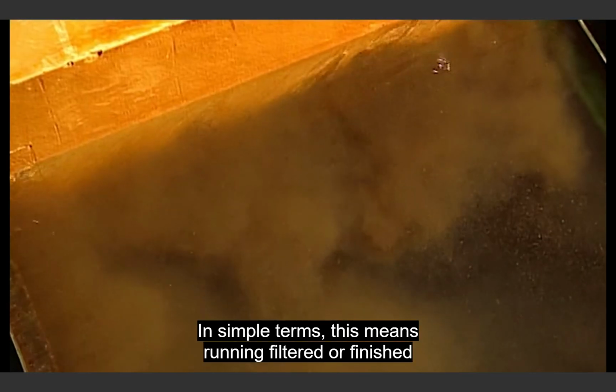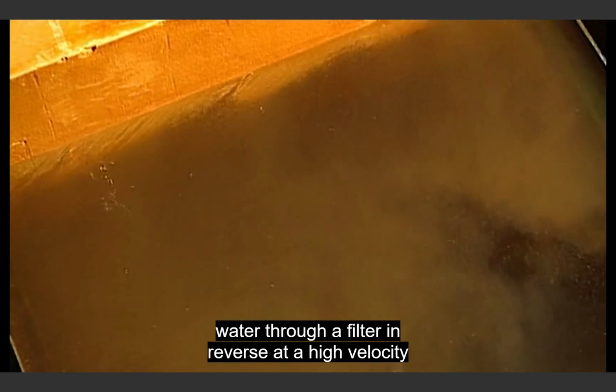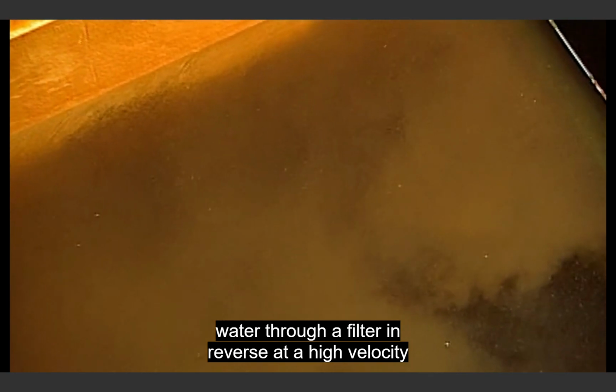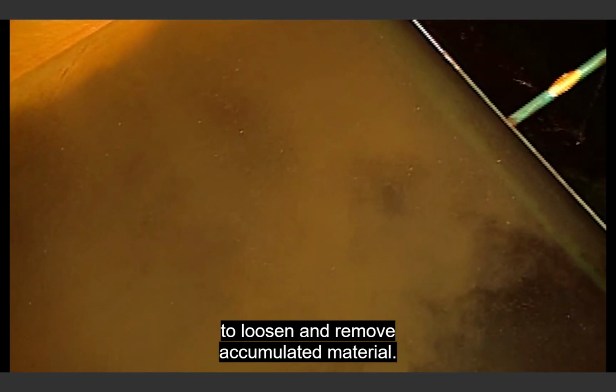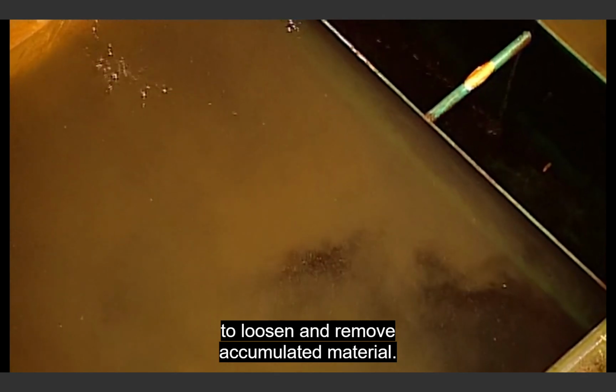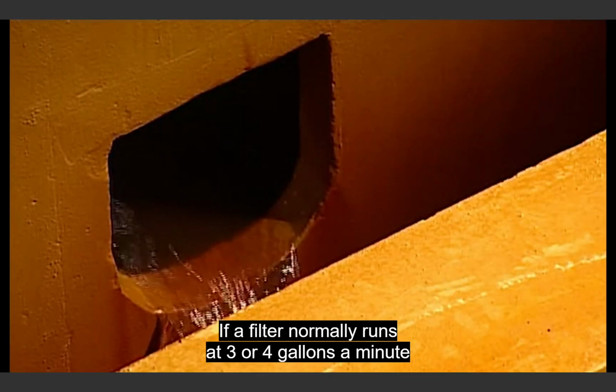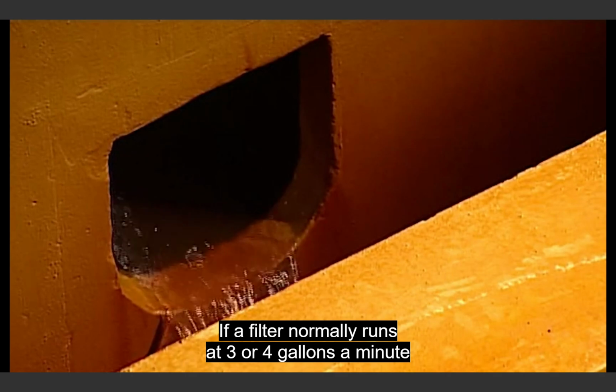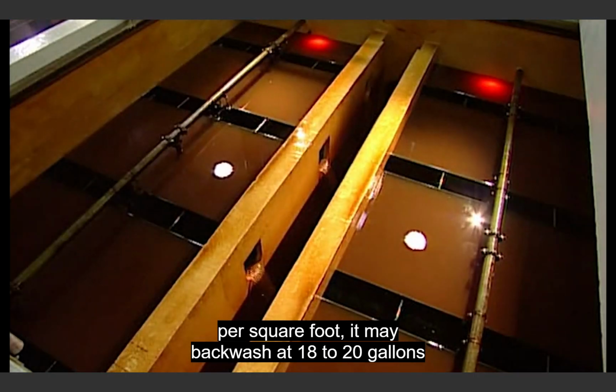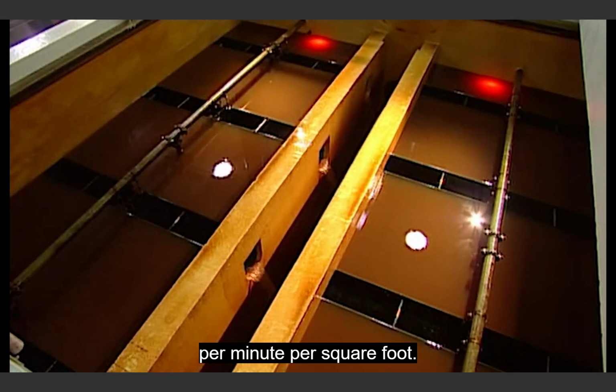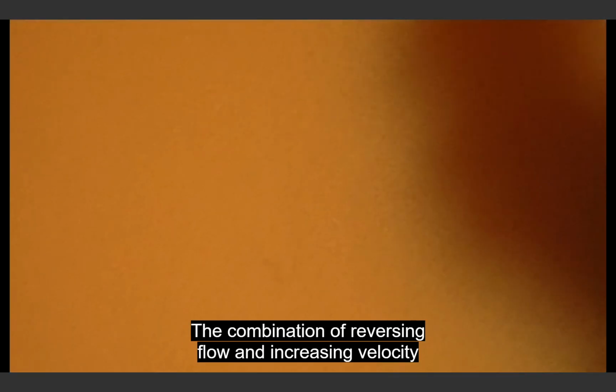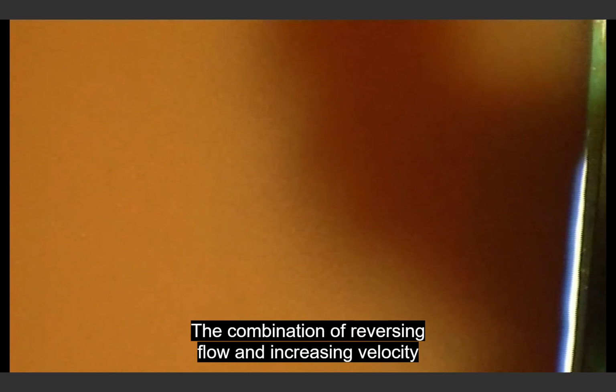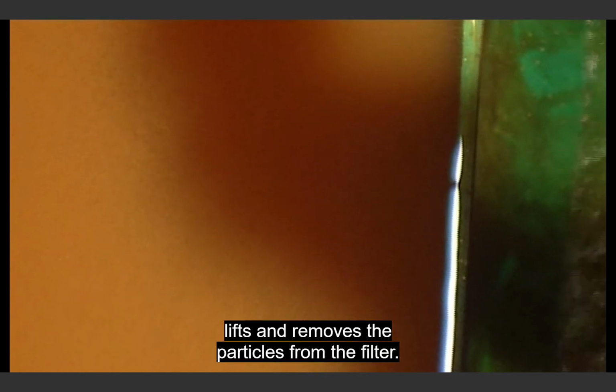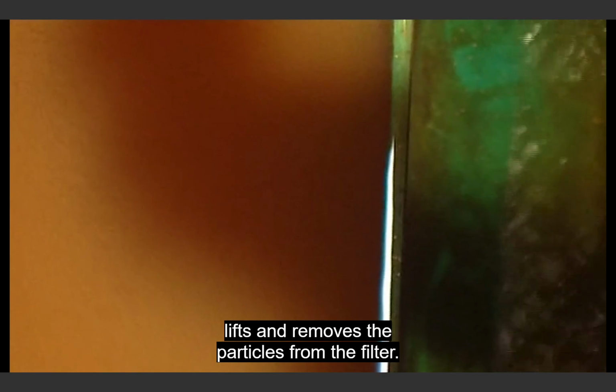In simple terms, this means running filtered or finished water through a filter in reverse at a high velocity to loosen and remove accumulated material. If a filter normally runs at 3 or 4 gallons a minute per square foot, it may backwash at 18 to 20 gallons per minute per square foot. The combination of reversing flow and increasing velocity lifts and removes the particles from the filter.